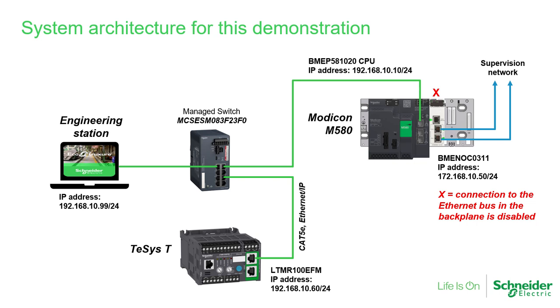We might also want to identify the CPU and NOC modules in the M580 PLC, specifically with their MAC address and firmware version. To remotely identify the CPU and NOC modules via the supervision network, explicit messaging will help make this data available in the PLC's registers, even when the NOC module connected to the supervision network does not have its communication enabled with the Ethernet bus of the backplane.